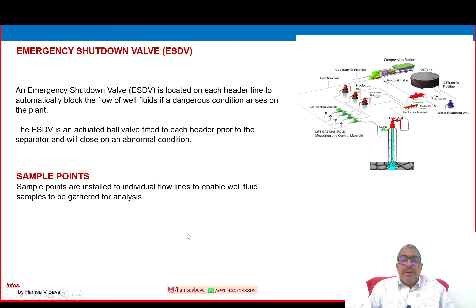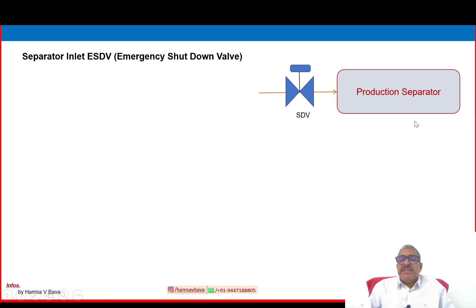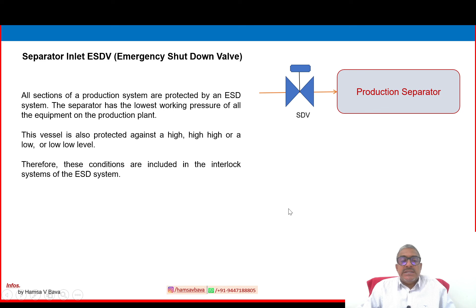Then the inlet separator. This is not a single piece of equipment; it is a number of equipment items connected in the gathering center, where the processing facility starts. Before that, one SDV is also provided to protect the downstream system in case upstream conditions are abnormal. All sections of a production system are protected by an ESD system. The separator has the lowest working pressure of all the equipment on the production plant. This vessel is also protected against high or low oil level or pressure. Therefore, these conditions are included in the interlock systems of the ESD system.